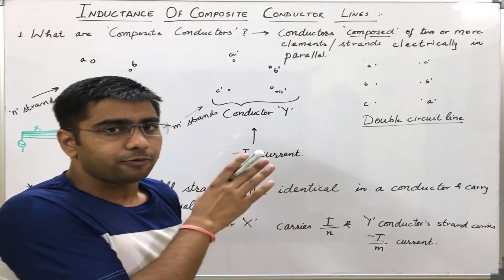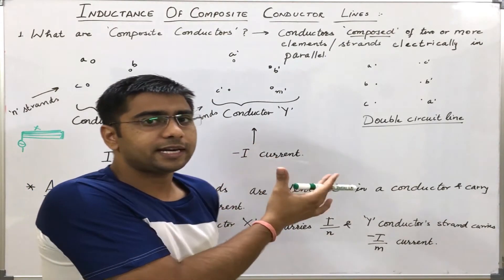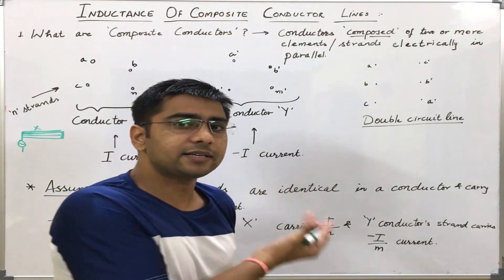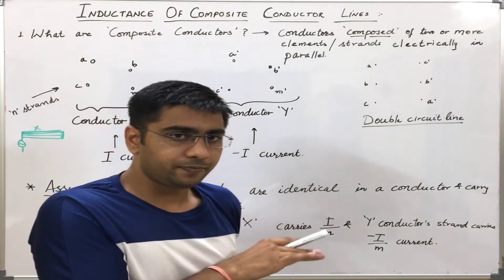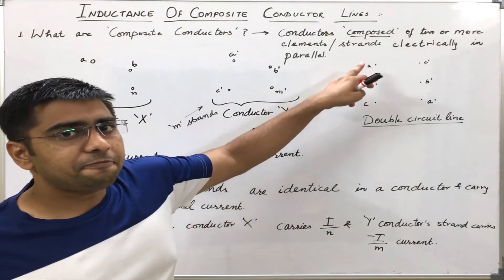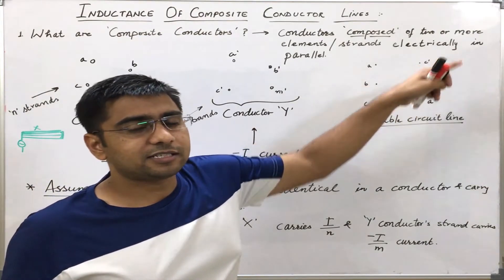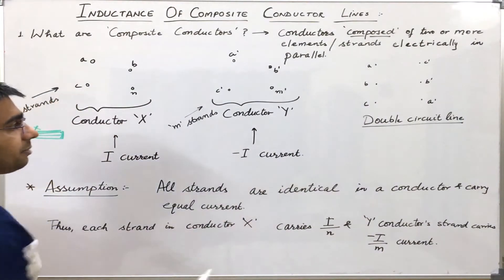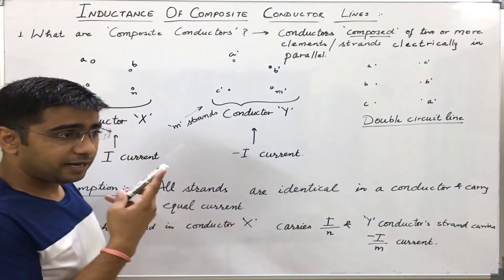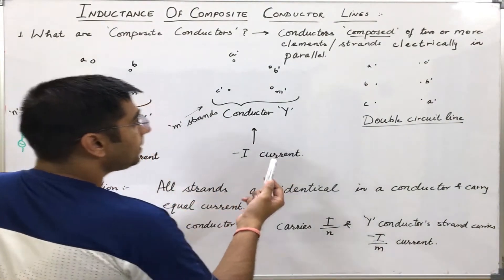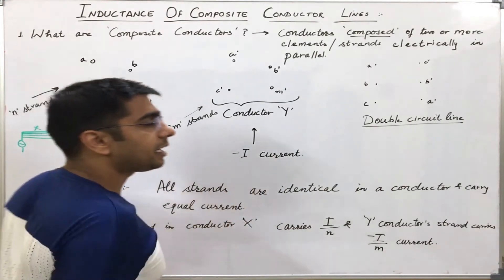To give a hint: what we want to do here is that we want to increase the geometrical mean radius of the system so that the inductance is reduced. That's why we are trying to place the same phase conductors at the maximum possible distance away. Similarly, C and C dash are being put diametrically opposite to each other. In this way, we are trying to reduce the inductance of the double circuit line.